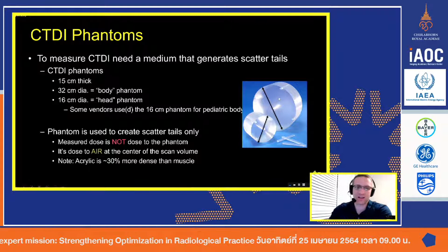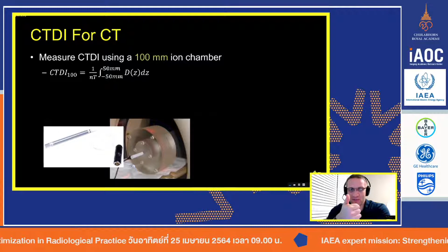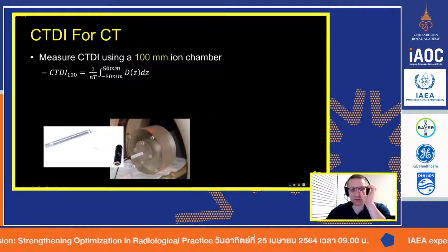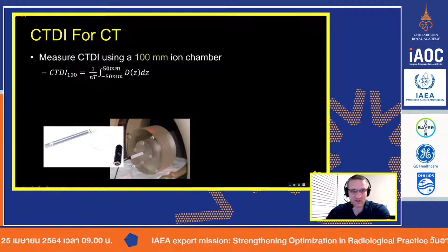But like I said from the beginning, CTDI is not meant to be, A, a patient dose metric, and B, it's not dose to the phantom. It's just there to cause scatter. We typically will measure the value for CTDI, the air kerma value at the center, using an ion chamber probe that is 100 millimeters long, or 10 centimeters. So we will put this in, we'll scan it, we'll integrate it. We're integrating over the length. We're summing the dose, or integrating over the length of the ion chamber.